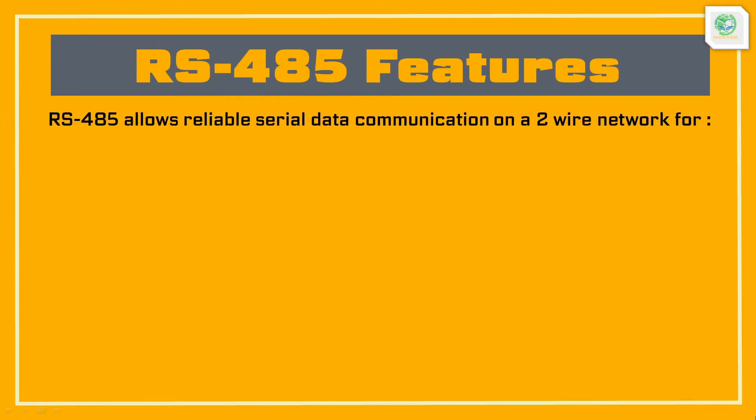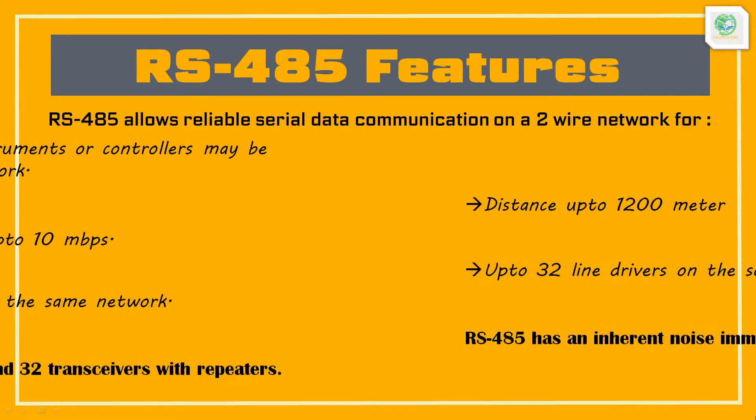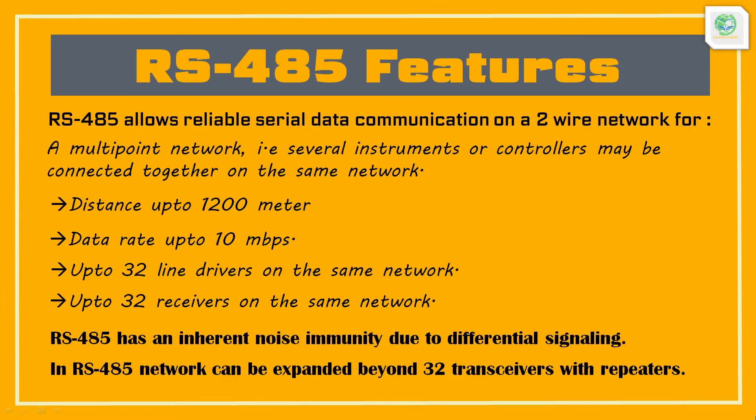If we talk about the features of RS-485, it permits a multi-drop network connection on two wires and allows reliable serial data communication for distances up to 1200 meters, data rates up to 10 Mbps, up to 32 line drivers on the same network, and up to 32 line receivers on the same network.